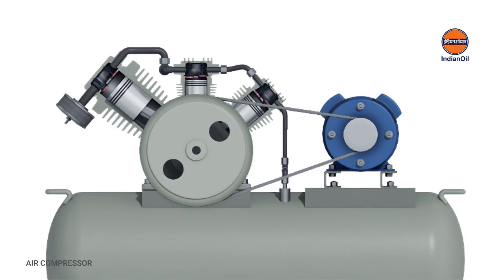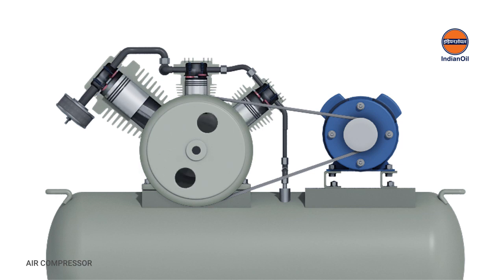These air compressors use this principle by pumping air into an air chamber through the use of the constant motion of pistons. They use one-way valves to guide air into and out of a chamber, whose base consists of a moving piston. When the piston is on its downstroke, it draws air into the chamber. When it is on its upstroke, the charge of air is forced out and into a storage tank.